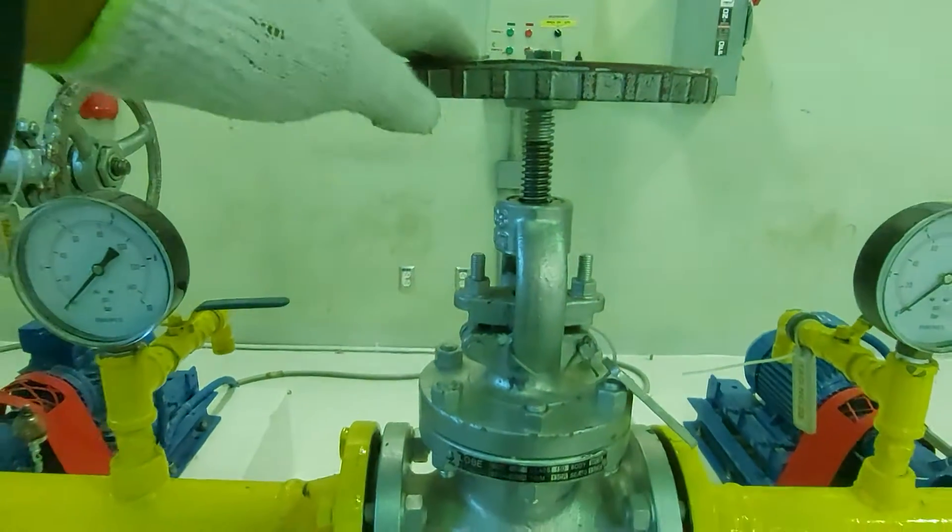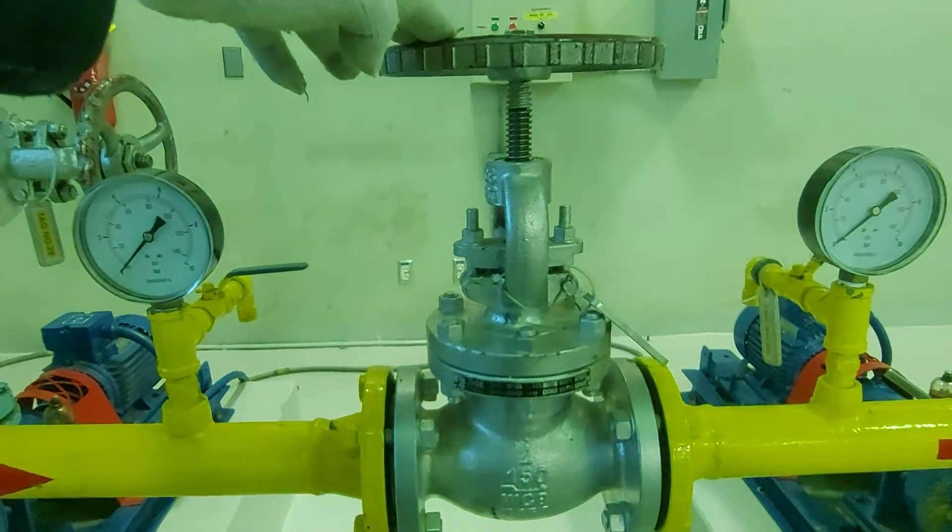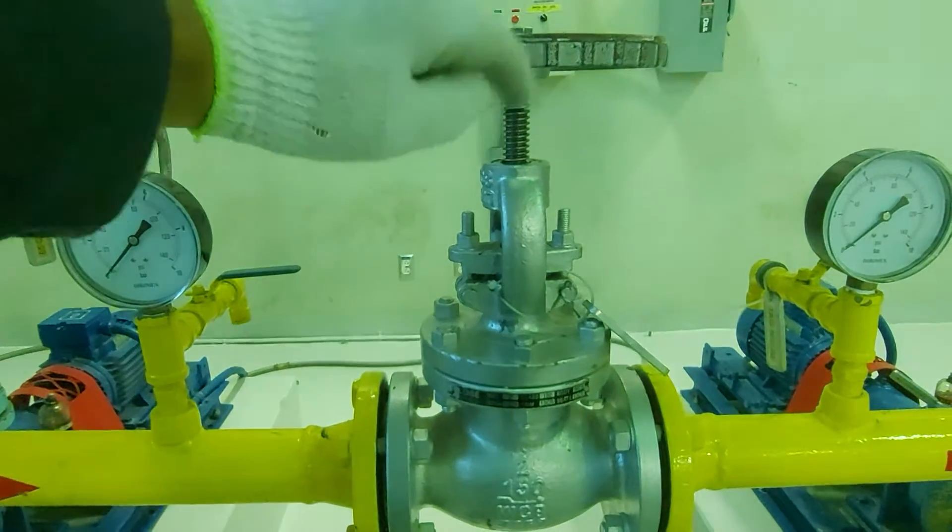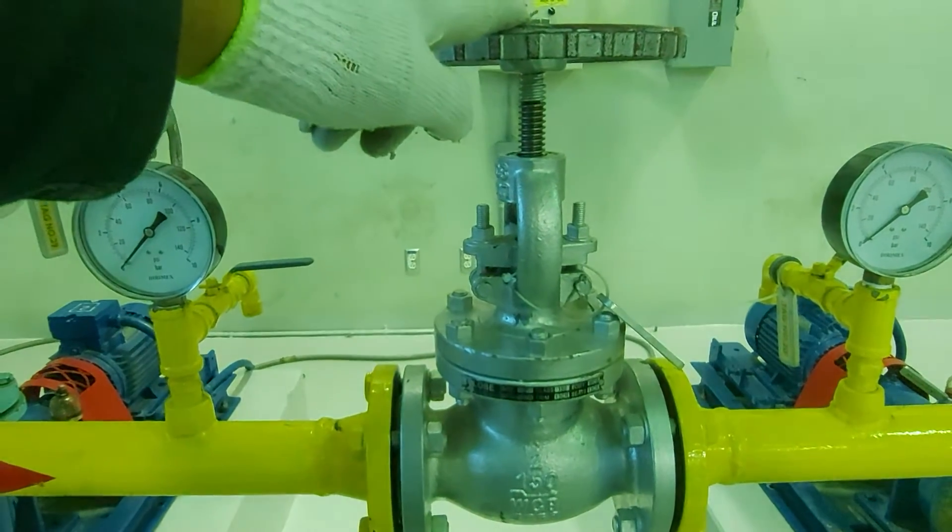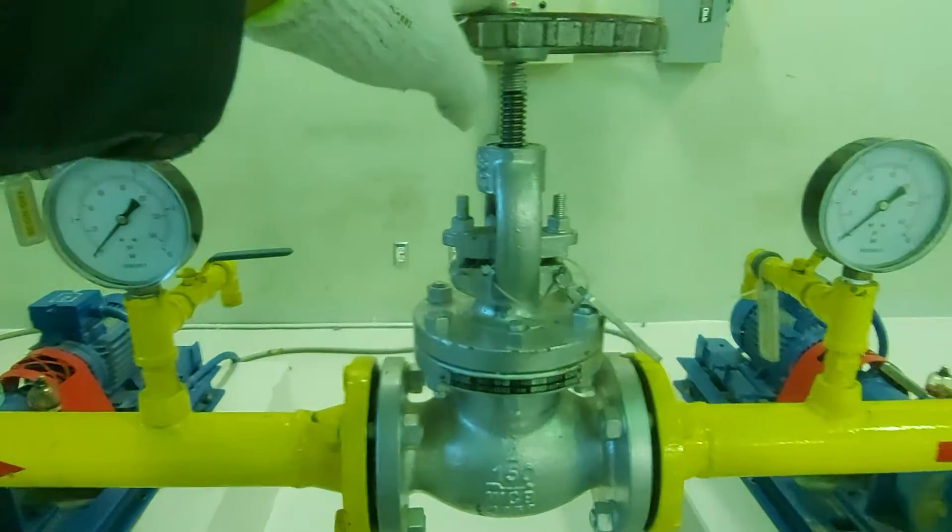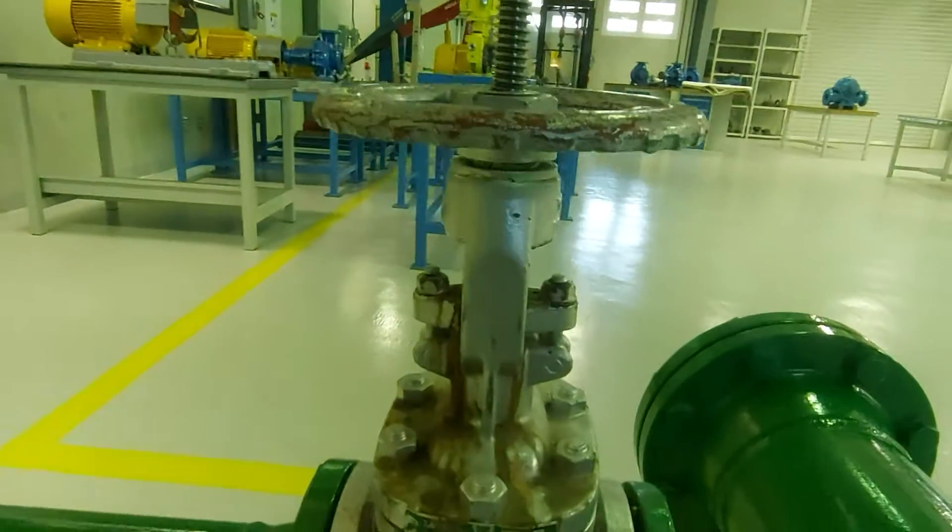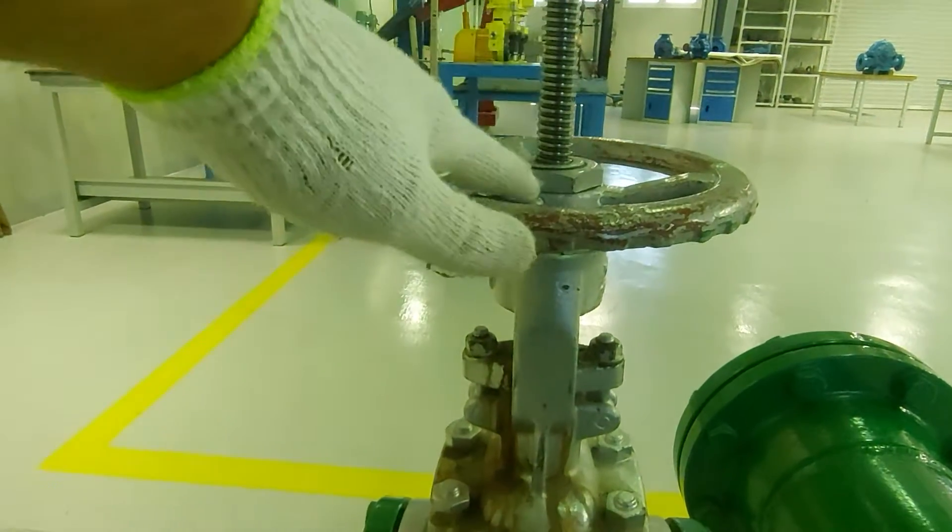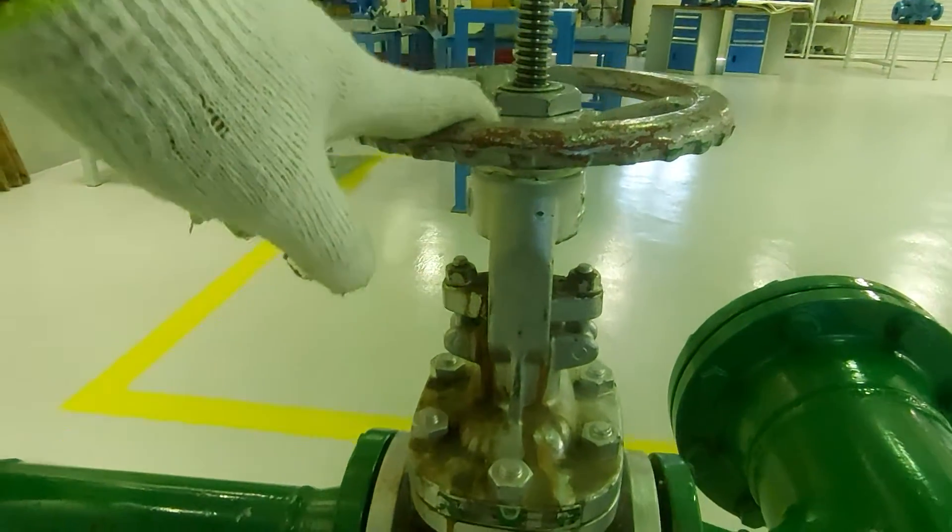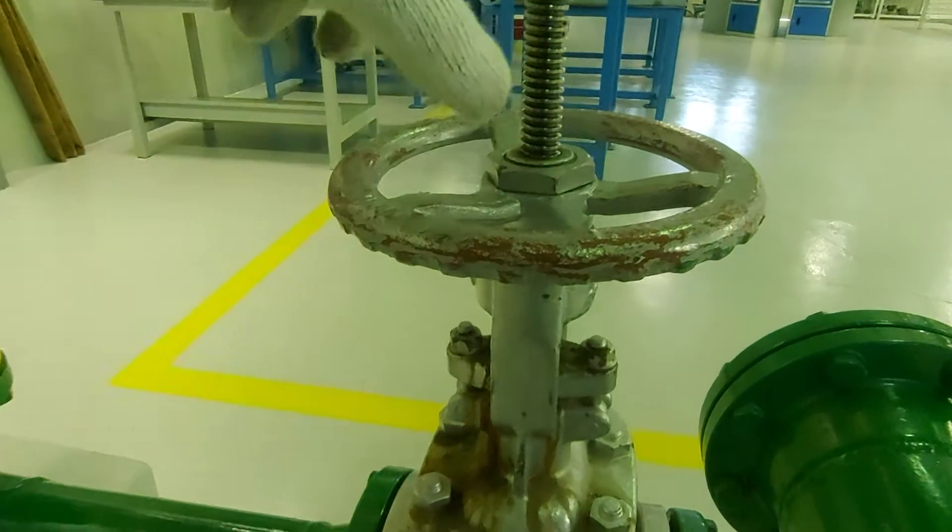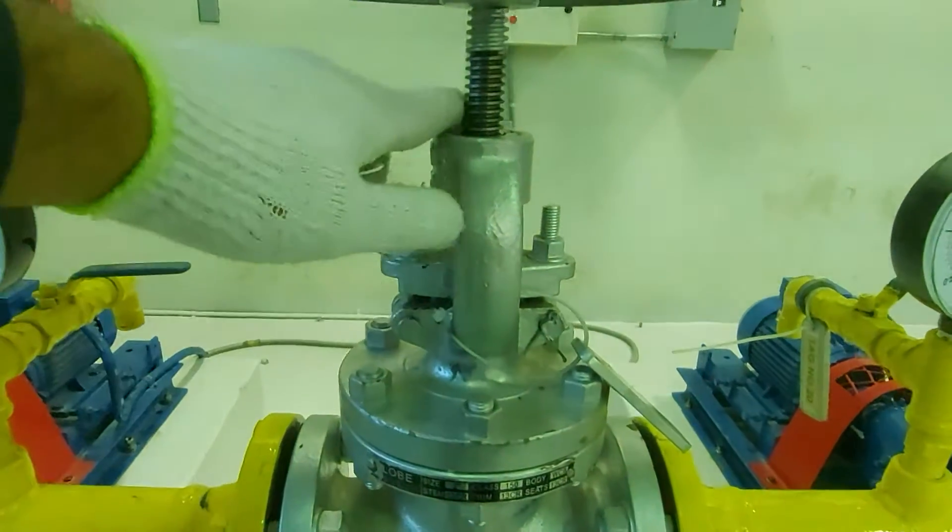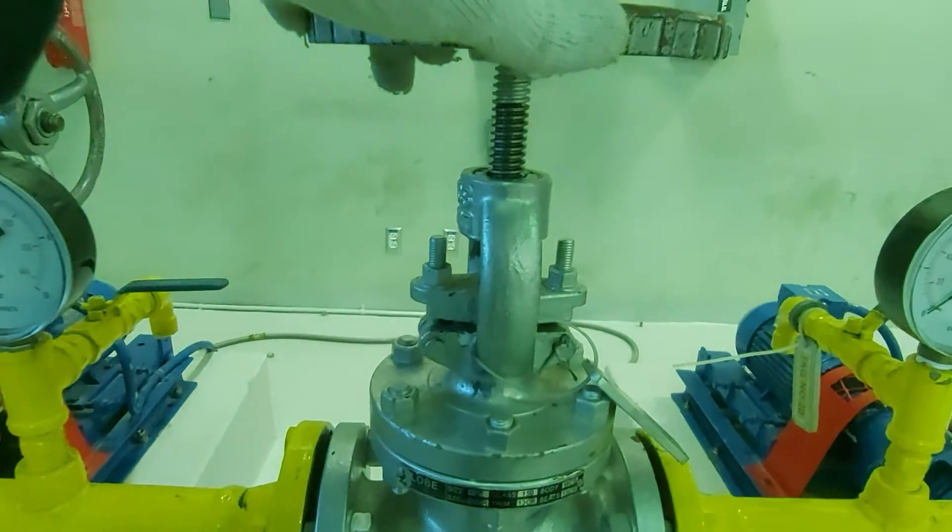So from far away you can tell that this valve is open when you see the stem below the handwheel, whereas a gate valve, you see the stem above the handwheel. So the gate valve is open, you see the stem above the handwheel. Here you see the stem below the handwheel, so you know that this valve is open.